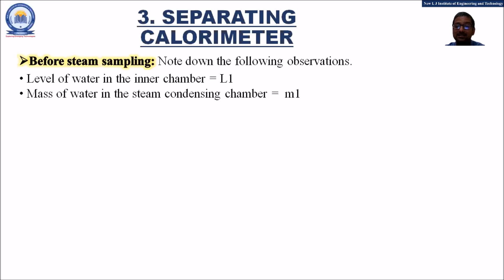During the steam sampling, what is the procedure we need to follow? Just understand the points. The wet steam enters the inner chamber of the separating calorimeter through a sampling tube which is controlled by a valve. While testing for the dryness fraction of the steam, the valve should be fully open in order to transfer the maximum amount of the wet steam.